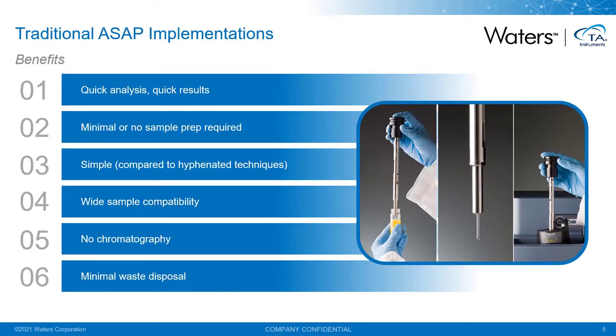Looking at the benefits of ASAP as an ionization technique, we find that it's a quick and versatile method which lends itself to rapid analysis with minimal requirements for sample preparation. The ionization process is essentially analogous to APCI and finds wide compatibility with different types of both sample and analyte. And as there's no chromatography involved, there's also a minimized need for the use and disposal of expensive solvents.